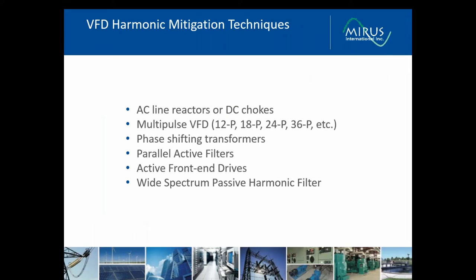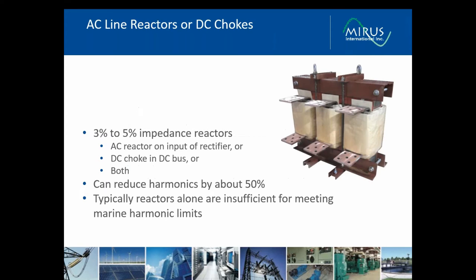So this slide shows a list of some of the typical solutions used in treating harmonics generated by VFDs, and I'll spend a little bit of time discussing each one. Reactors, both AC or DC, are very commonly used as a form of harmonic mitigation. They can typically reduce current harmonics by about 50%. This may seem like quite a bit, but it is rarely sufficient to meet marine harmonic limits. And increasing the reactor impedance to reduce current distortion further is not possible because it will introduce voltage drops that will cause VFD misoperation.